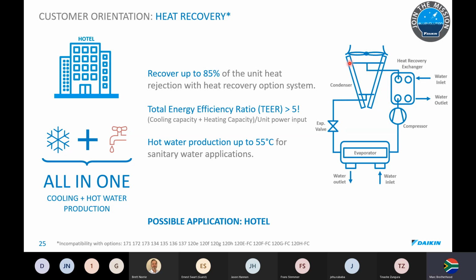And the condenser fans don't have to spin that much. So besides you getting hot water, in inverted commas, for free, your condenser fan is going to be a huge energy saving because it's not going to be spinning that much. And in this specific chiller, with this double V-block assembly, you can easily get up to 55-degree water for showering. And it's ideal, for example, for hotels, storage water.